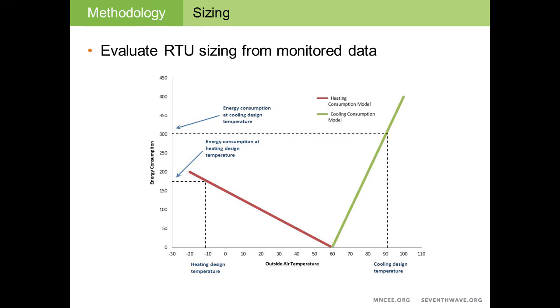So once we had this data, we wanted to look at the ability to evaluate sizing considerations for rooftop units. Traditionally, if you wanted to look at sizing for a rooftop unit, you would compute the internal heat loads, the heat requirements, the cooling requirements, and then assess your building envelope for heat loss. We weren't able to do that just because we didn't have a lot of information on the building components itself. So we elected to use the actual monitored data to evaluate the sizing of the rooftop unit. We would develop from the interval data, 15-minute data, the energy consumption as a function of outside air temperature, develop a model, and then apply the design cooling and heating temperatures to those two separate models and evaluate the energy consumption at design conditions.